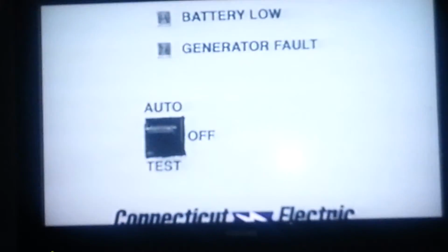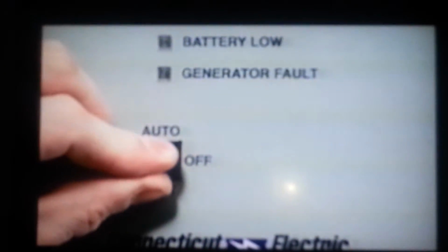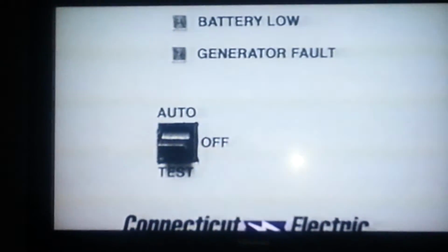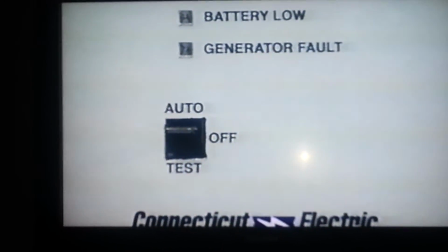To test the ATS transfer switch, you must first turn on the double pole breaker in the service entrance panel, which is connected to the transfer switch. To test the generator, move the auto off test switch on the transfer switch to test position. The green all OK light should come on, and the generator should start. Move the auto off test switch to the off position to stop the generator. If the generator does not start, consult the troubleshooting section in your installation instructions.